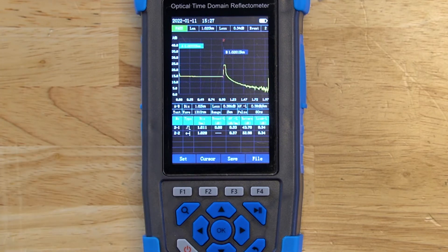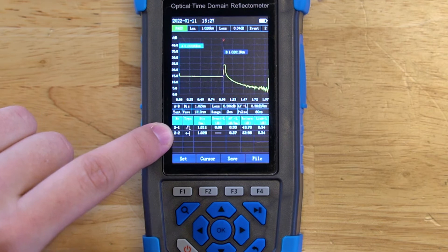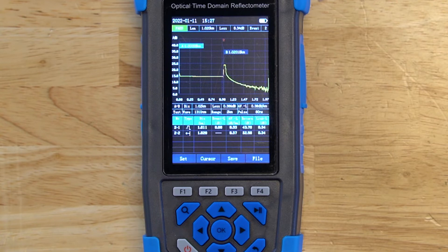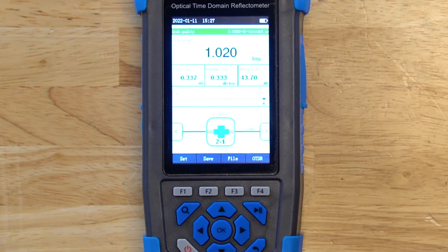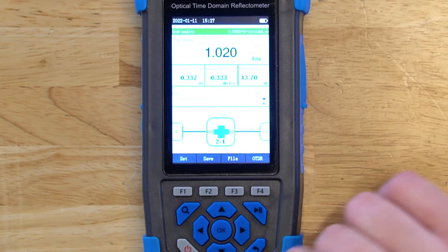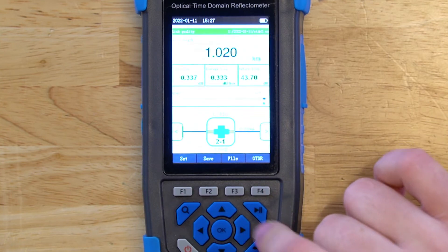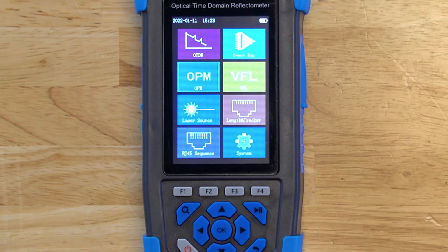There are four different symbols that could occur. The first is a reflective event, shown in 2-1 — this is when there is a connector, a mechanical splice, or a break in the cable. A non-reflective event looks like a step of a stair and is usually for bends in the fiber or fusion splices. The OTDR-1000 can also detect splitters, so there's a separate symbol for that as well. When you're done, you can press back to go to the event map, save the file, rerun the test, or load a different file.